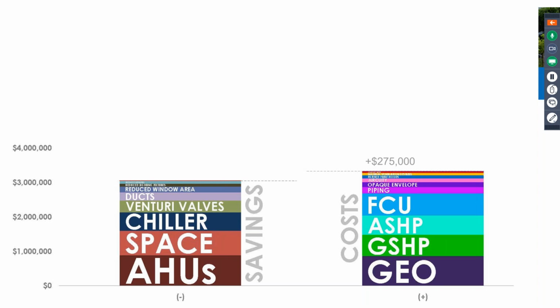Now, of course, that turned out to be a little bit too good to be true. We went back at the end of construction with all of the final construction costs and updated the analysis. And it turned out that the cost premium to get to net zero was $275,000. But that is 1% of the construction costs for the project. That still seems too good to be true, but if you look at this graph, what it's showing on the left is all of the things that we were able to do to reduce construction cost. So the air handlers went from over 70,000 CFM down to 24,000 CFM by reducing the loads and by putting fan coil units in the spaces. We also reduced the size of the penthouse. There originally had to be two penthouses, one on either side of the atrium, and we were able to eliminate an entire penthouse. We also eliminated the conventional air-cooled chiller and reduced a significant amount of valves and ductwork for the lab air.